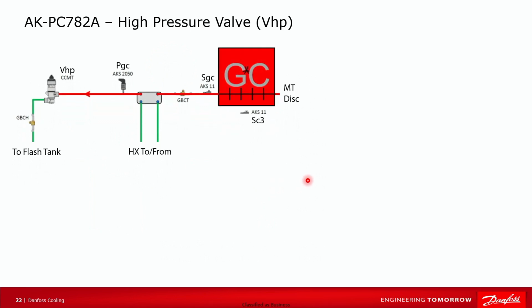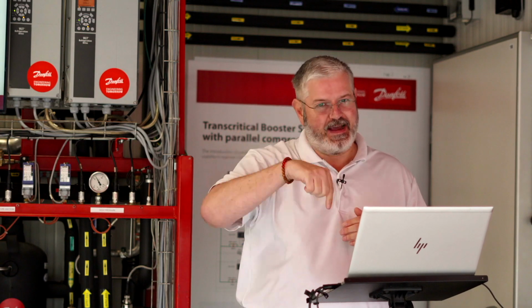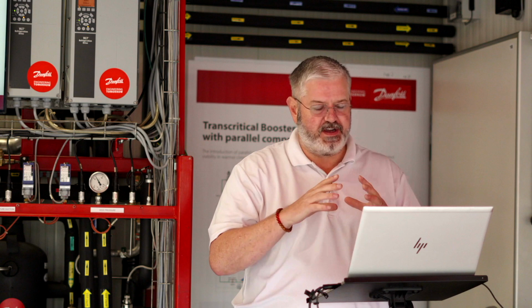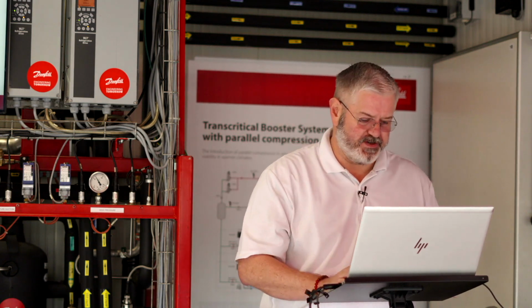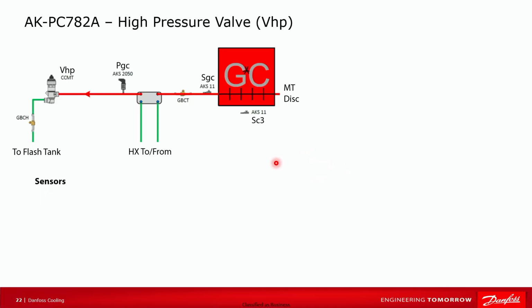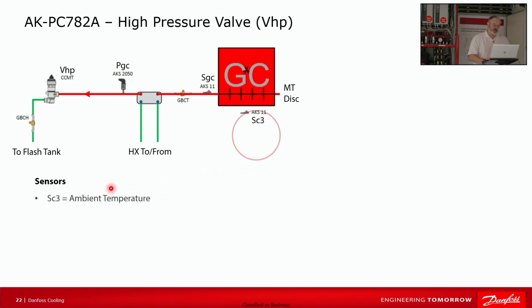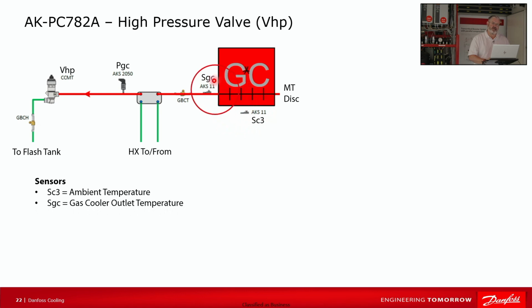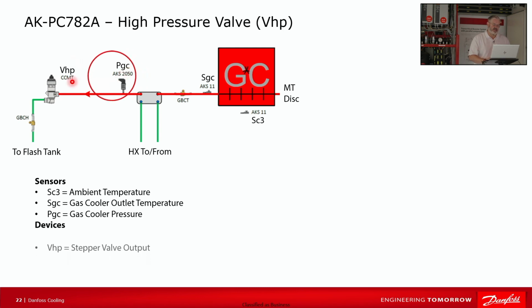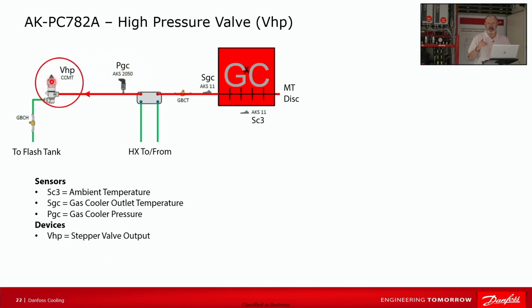So the high pressure valve, this is one of the two new components that we need. If you'll remember, to get from the high side of the system in the supercritical fluid region down into the dome where we have liquid and we can change state and do work, we needed the high pressure valve. The way this controls is kind of interesting. So the sensors, it makes reference to the ambient temp. The gas cooler outlet temp is extremely important to it. We've got a pressure on the gas cooler outlet. And then as far as devices, it's just the stepper valve itself. It's the high pressure valve.